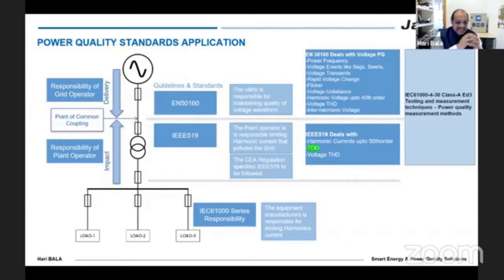This is a very important point which I wanted to get across. If you look at the standards, there is a distribution company which is delivering power to the consumers, and there is a point of common coupling where they transact energy. That is, the distribution company is shaking hands with the consumer and giving power to the consumer, and that point is called the point of common coupling. In essence, the standard EN 50160 is to be maintained by the utility. So if a utility says it is maintaining the EN 50160 standard, it means they are giving a good power frequency, a good quality of power without sags and swells. There is no voltage change, the flicker is less, and voltage unbalance is within the limits of EN 50160. Harmonics for the voltage up to the 40th harmonic is maintained according to EN 50160, and of course interharmonic voltage. So when the utility says that EN 50160 is maintained, it talks only about voltage.